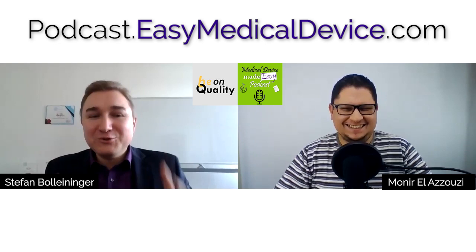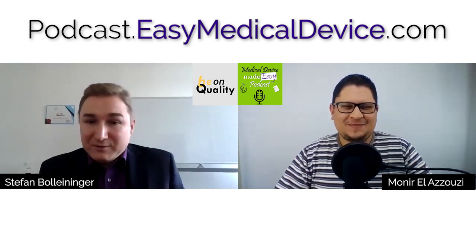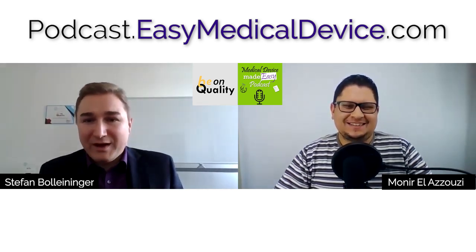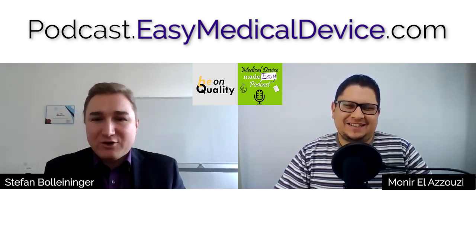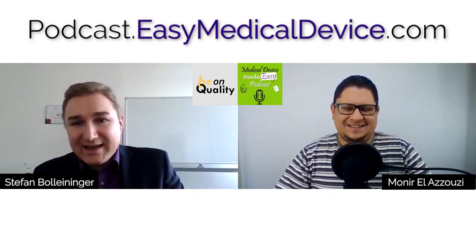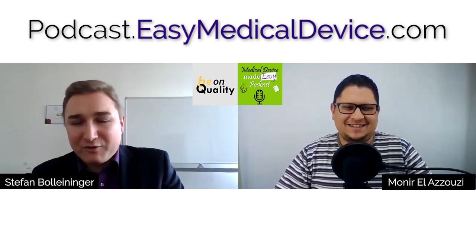So I would do it in one, and that is with the one with the highest requirements, and that's a notified body. I would do it in one because they can share the audits, they can look into it briefly, they can say, okay, I have checked this, and that implicates the other process, and that's easier. It's clever, it's cost saving, and it's easier for the one who performs the audits.